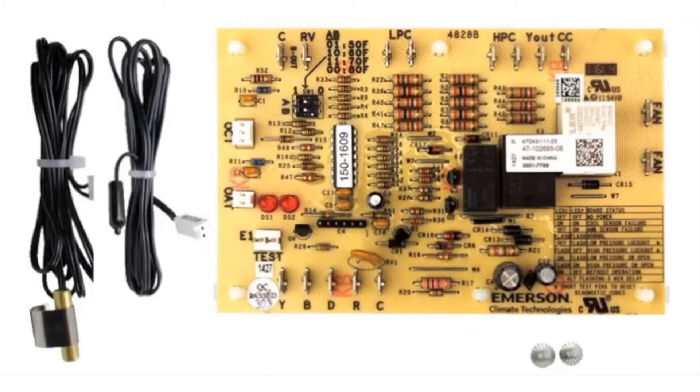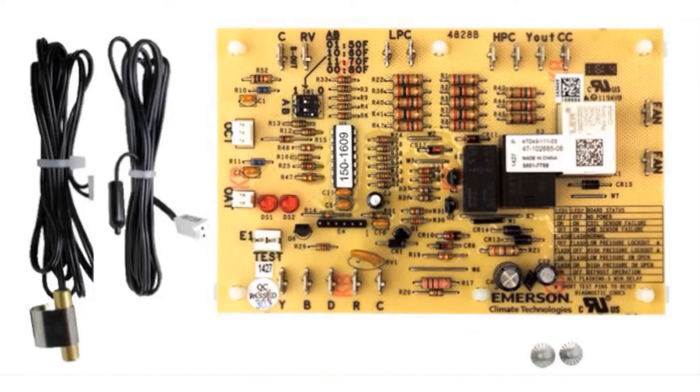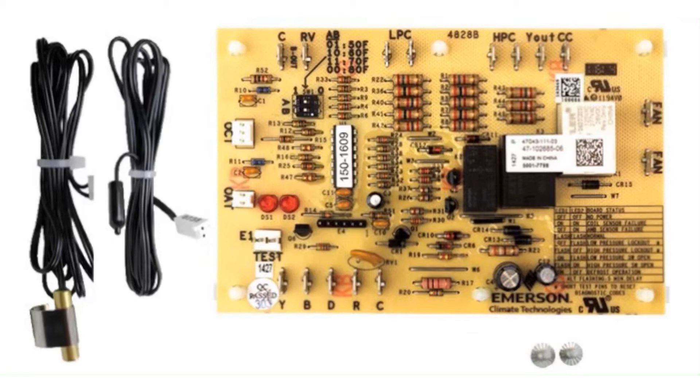All right. So you've got a couple options here. When you need to replace the sensors, you can pick them up separately. They come in a pack, one for the coil, one for the outdoor ambient. Or if you pick up the defrost board itself, it will come with these sensors in the box with it. So remember when we're replacing the defrost board on the heat pump, always replace the sensors as well.